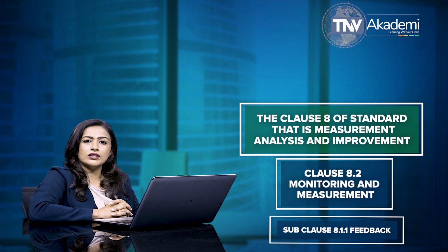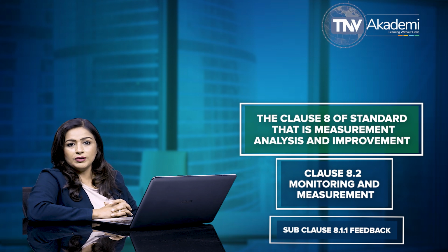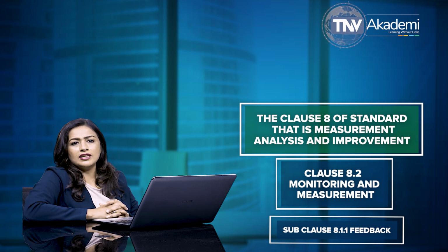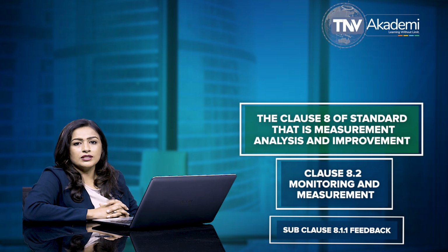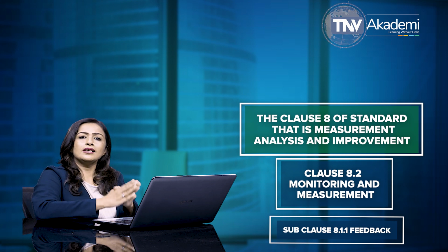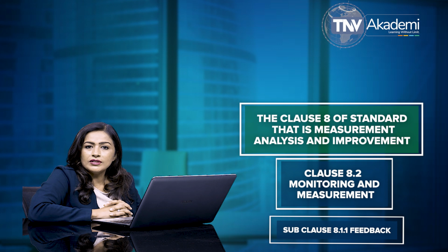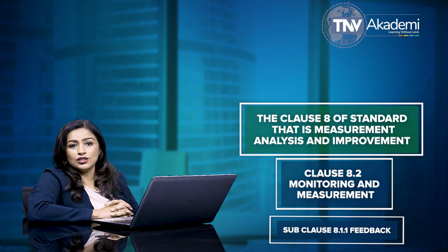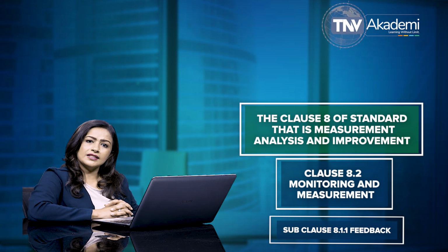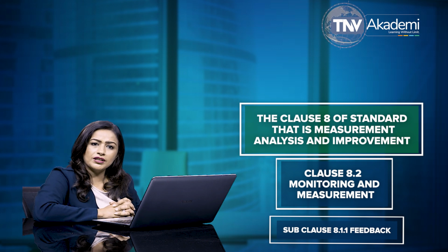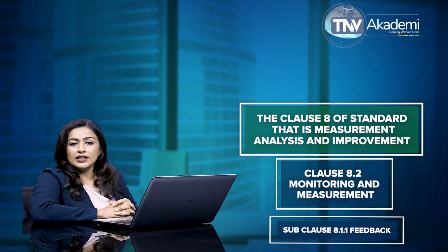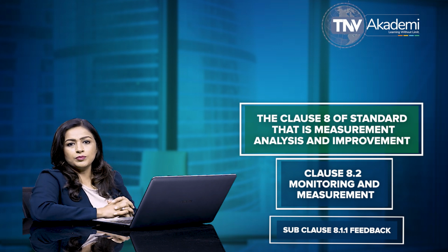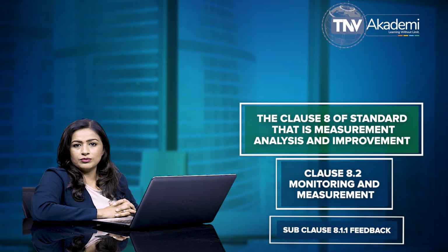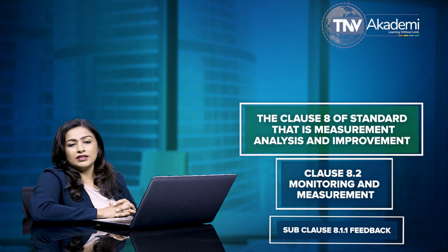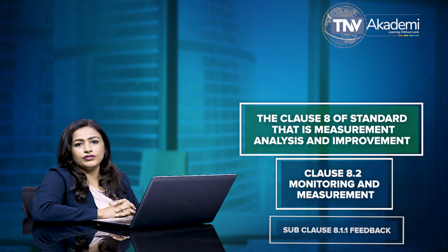According to this subclause, the information gathered in the feedback process must serve as potential input into risk management for monitoring and maintaining the product requirements as well as the product realization or improvement processes. The subclause further states that if applicable regulatory requirements require the organization to gain specific experience from post-production activities, the review of this experience must form part of the feedback process.